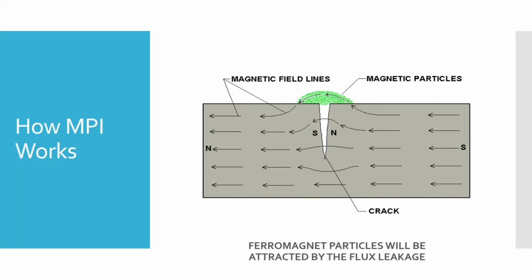And so as it's jumping, we put some magnetic particles there, and you can see they get trapped in that little jump of magnetic flux. Something like that. And that's what becomes visible. Then we have these ferromagnetic particles. They can be two types. They can be just dark colored or colors. You can get these little magnetic particles or iron particles, or basically iron filings, iron shavings.